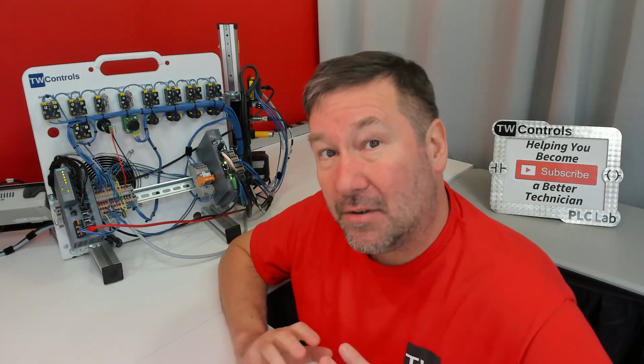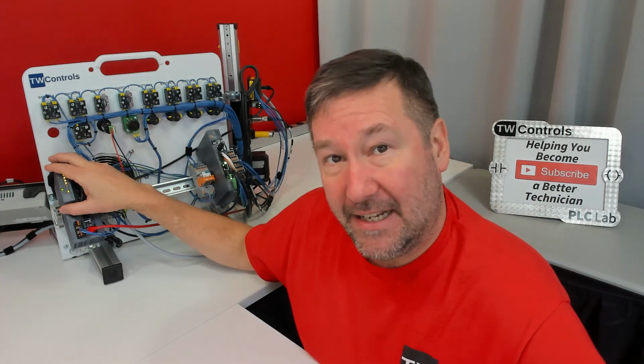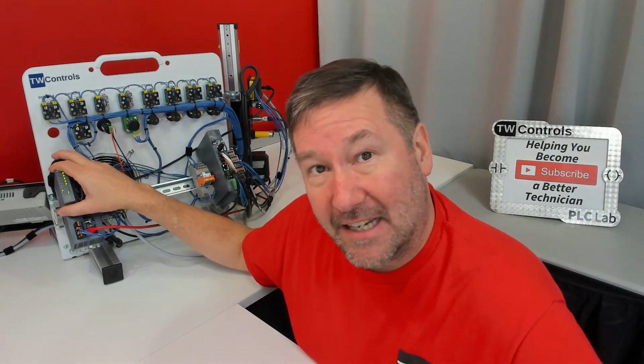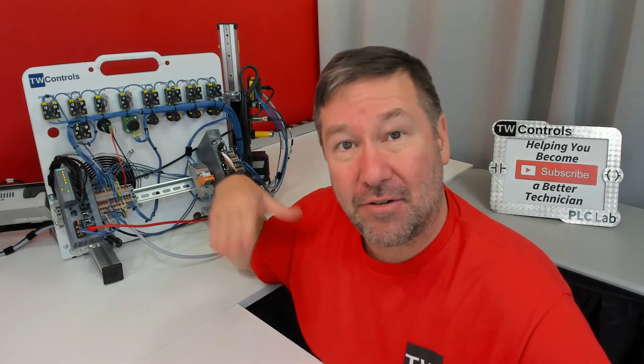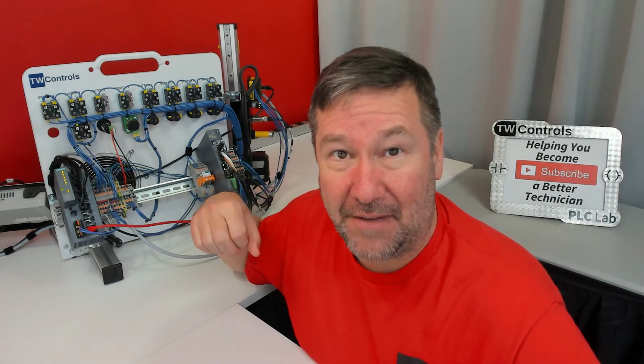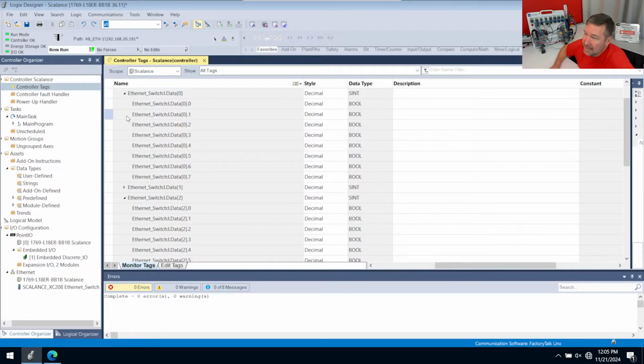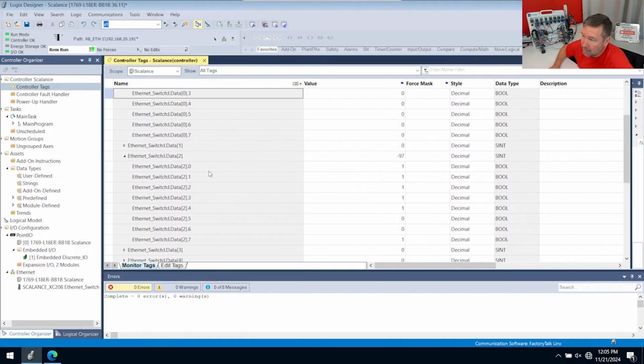Previously, we installed the third-party EDS file for our Siemens Scalance Ethernet switch, and we added it to our I/O configuration in Studio 5000. And we discovered that Ethernet switch :I data 01 was power source 1, and 3 was power source 2, and whether our ports were active or not was in 2.